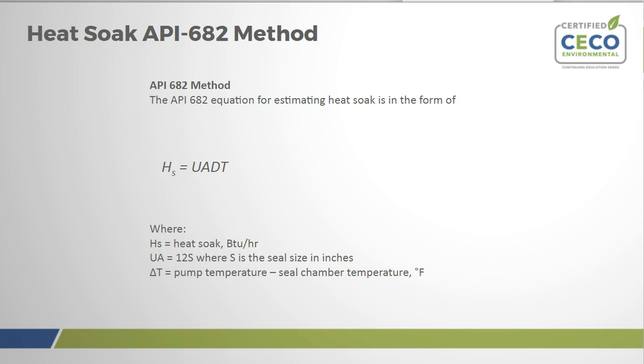We generally like to keep the seals under 350 degrees. That seems to be where they operate best, at the most reliable, and give you the best performance and longevity. So if we're operating at 650 degrees, we want to bring that seal temperature down to 350 degrees. So the heat exchanger is going to be required to drop 300 degrees.